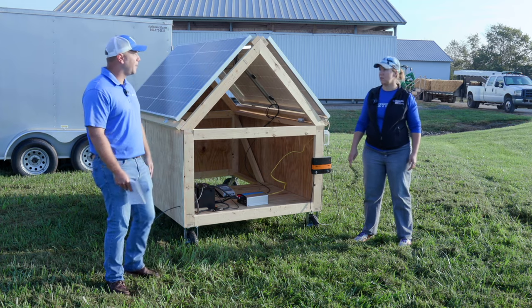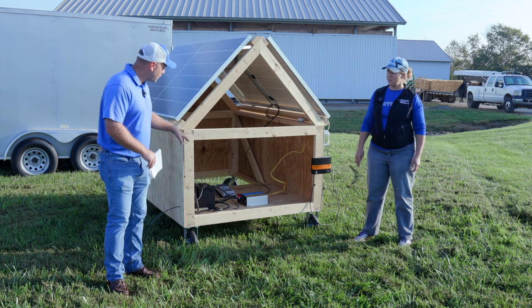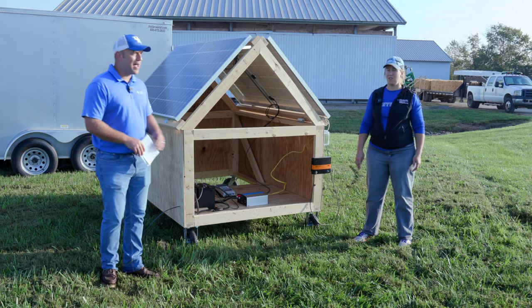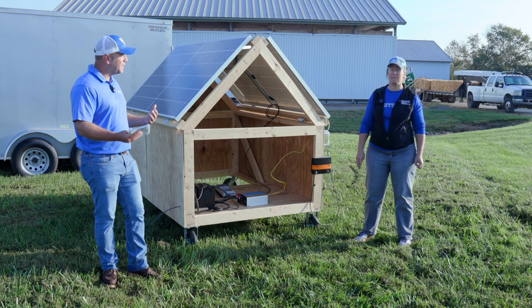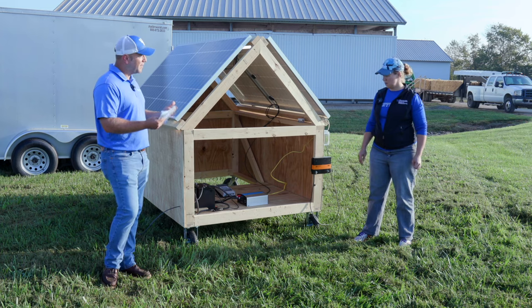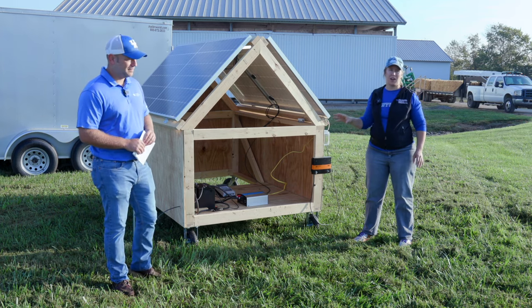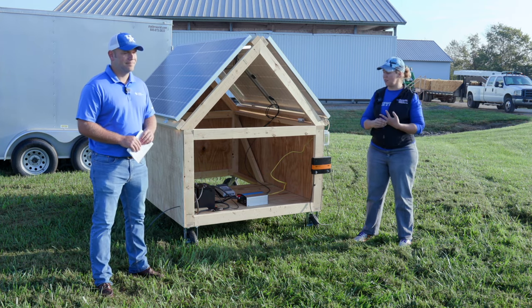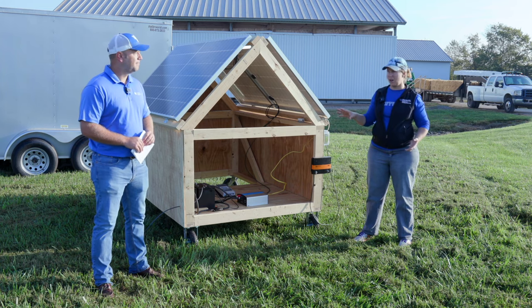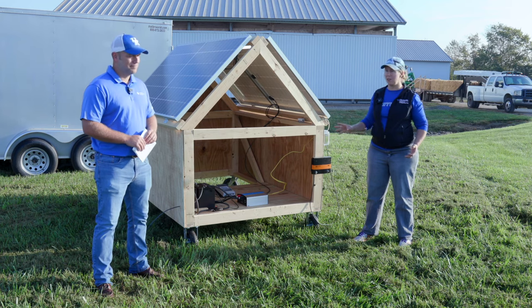We've got batteries — that's probably the next most important part of a solar installation. What we have is two lead acid deep cycle batteries. There are lithium batteries out there too. The lead acid batteries are by far the cheapest option and the most accessible — ones you can buy at a lot of different places and that a lot of people already have on their farm. The lithium batteries handle heat and cold a little bit better if you have a lot of temperature swings. They are more expensive, but they do have a longer lifespan.